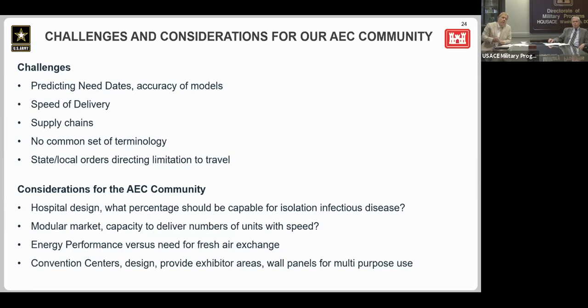Talk a little about the modular market and energy performance. This came up in the last series with New York. It's a concern that here we are trying to build buildings tighter and tighter, limit fresh air exchange, recirculate conditioned air, and in the face of a pandemic, you say, no, 12 air changes per hour is what we need. Do we HEPA filter and exhaust 100%, or can we HEPA filter and recirculate? On the pre-filter design, what is the right number for energy performance? Can you build the building for energy performance and then switch over, throw a few switches, and divert, and have something for a pandemic and infectious isolation, negative pressures, et cetera?